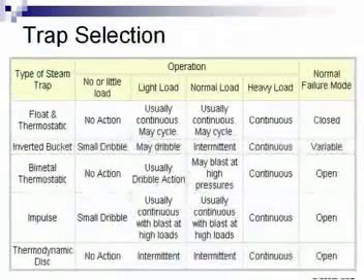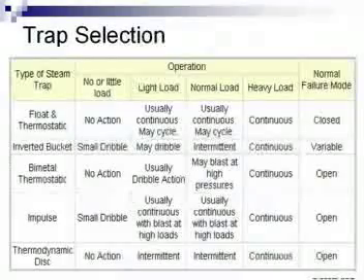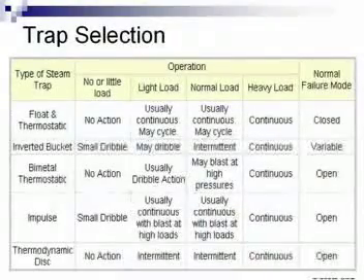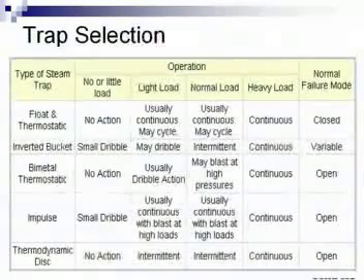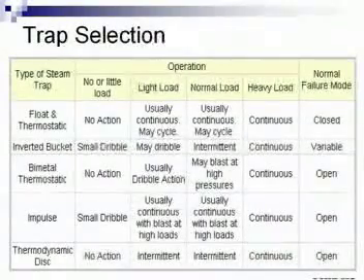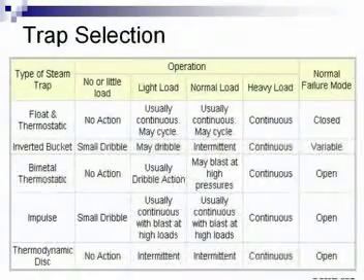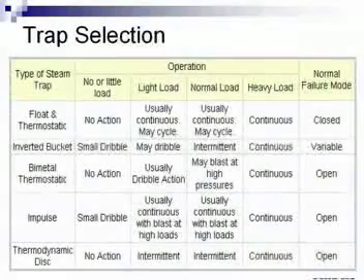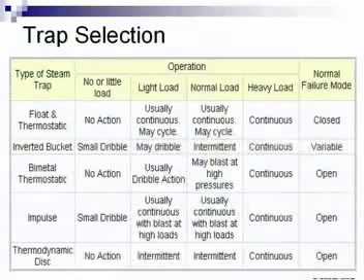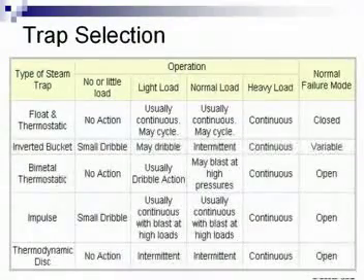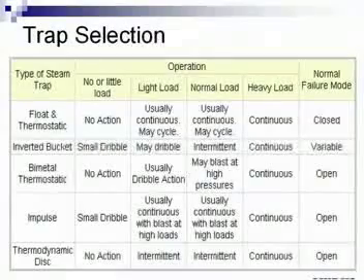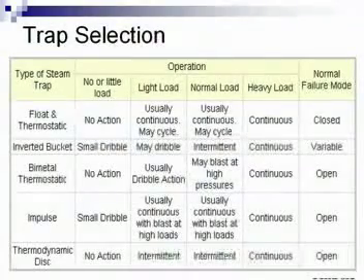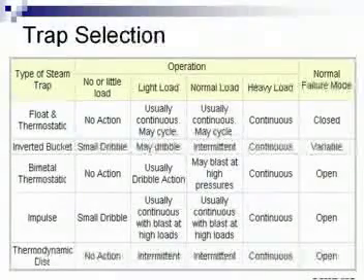Trap selection is imperative — the proper trap must be applied to the proper situation. If you notice to your left, there are five different styles of steam traps. In the center we discuss operation and typical failure modes. For example, looking at a float and thermostatic trap — when we talk about load, we're talking about the amount of condensate the trap is sized to remove. On light load it would usually cycle continuously; on normal load it would be usually continuous and may cycle; on heavy loads it would be continuous. Normal failure mode for a trap like that may be in a closed position. Inverted buckets, bimetallic, and impulse traps all have specific operating conditions that fit specifically in your system.